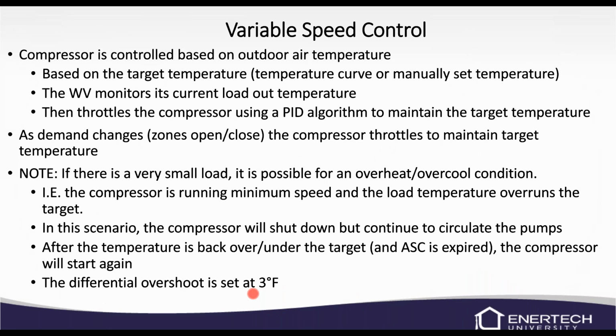The compressor is controlled based off outdoor air temperature and a target temperature, so the temperature curve or the manually set temperature. It's going to monitor the load out temperature, and it's going to throttle the compressor using an algorithm to maintain the target temperature. Over time, the unit will learn more and more how quickly it needs to react. It's kind of a little learning process. So it'll throttle the compressor to maintain the target. As the demand changes and more zones open or close, the compressor again will throttle to maintain that delta T across the heat exchanger.